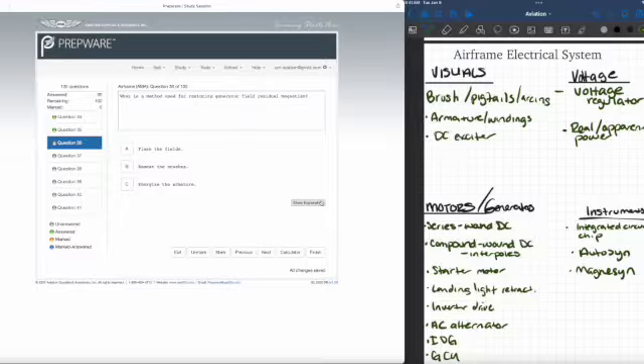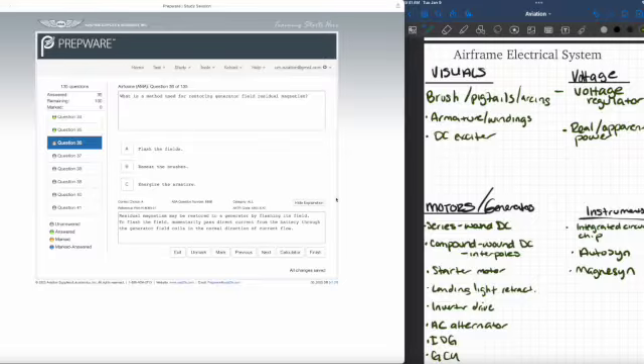So, what is the method used for restoring generator field residual magnetism? A. Flash the fields. Residual magnetism may be restored to a generator by flashing its fields. To flash the field, momentarily pass direct current from the battery through the generator field coils in a normal direction of current flow.